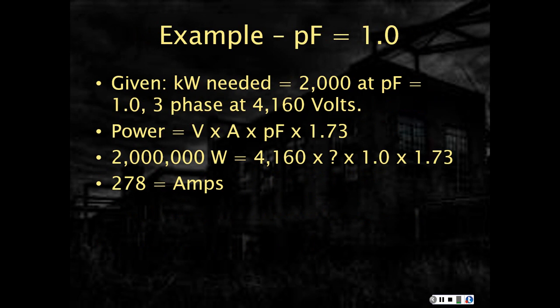So given, if I have a power factor of 1, the kW that I need in my building is 2,000 kilowatts. Now, if I have a power factor of 1 and a 3-phase electrical distribution system at 4,160 volts, if we use the power calculation, volts times amps times power factor times 1.73, and solve for the amp draw that I need, the amps come out to 278 amps.